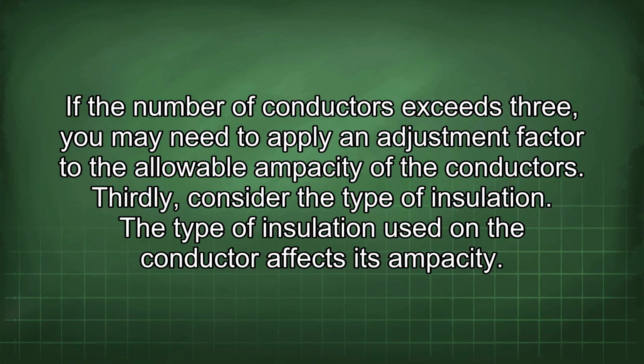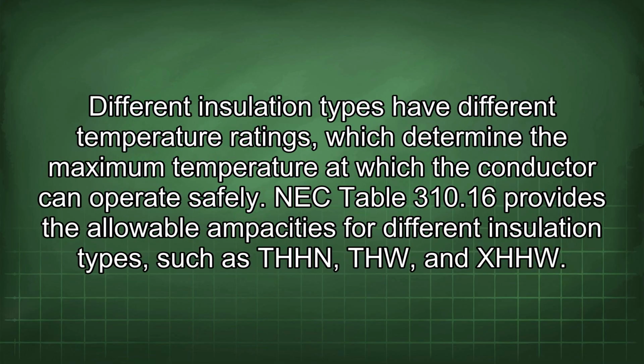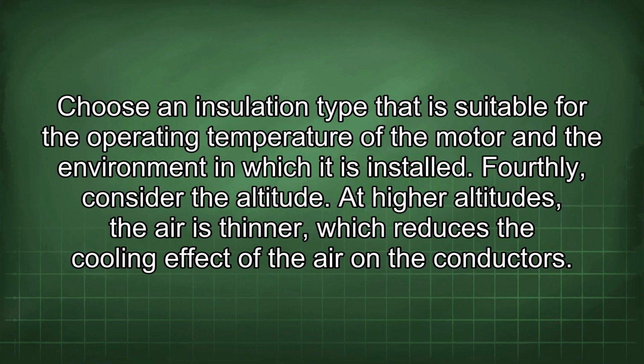The type of insulation used on the conductor affects its ampacity. Different insulation types have different temperature ratings which determine the maximum temperature at which the conductor can operate safely. NEC Table 310.16 provides the allowable ampacities for different insulation types, such as THHN, THW, and XHHW. Choose an insulation type that is suitable for the operating temperature of the motor and the environment in which it is installed. Fourthly, consider the altitude.